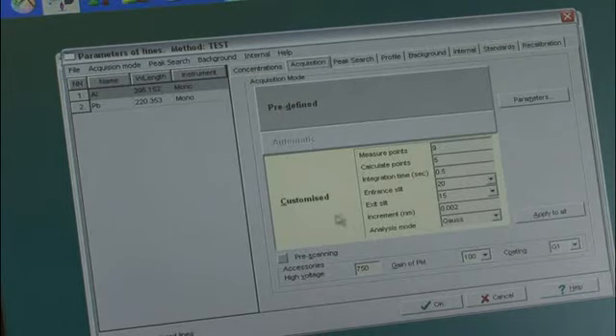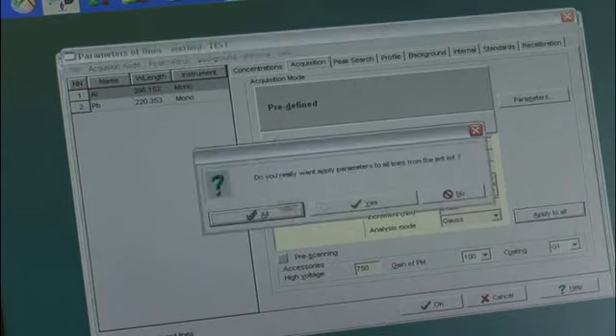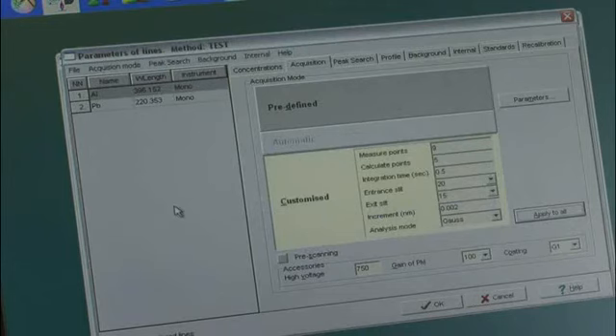So I'm going to leave this as customized and just click apply to all, and I'll say yes. Now, as you go up in wavelength, the peaks will get broader, so I may want to increase the steps for my aluminum peak to say 4 picometers per step, because otherwise it'll be very wide when it analyzes. So if the increments are larger, then the peak will be more defined.